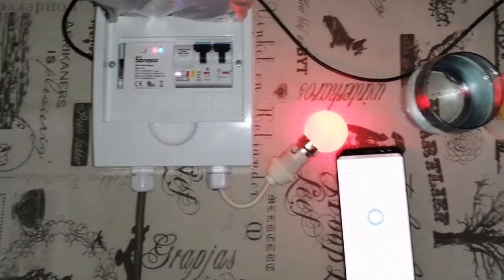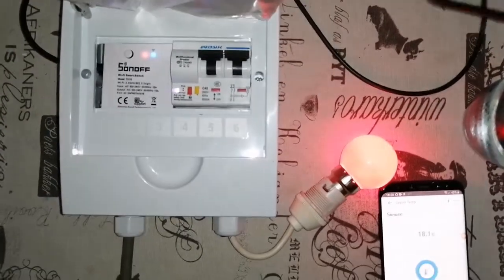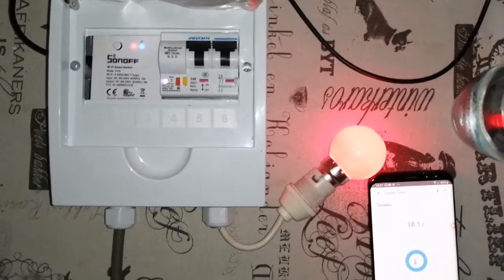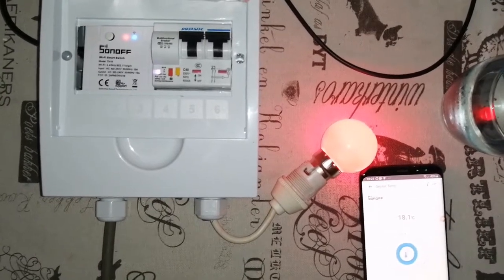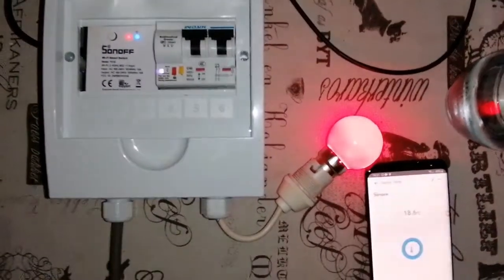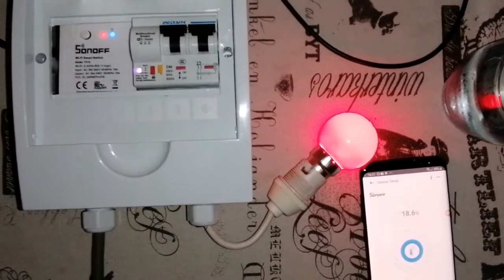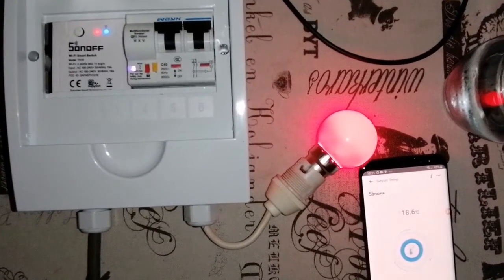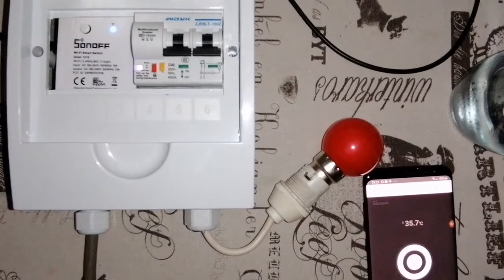Let's quickly just see what happens to the two switches. It is on — less than 25 degrees. I'm going to put it in the hot water. What will happen now is once the temperature reaches 30 degrees, the TH16 will switch off, and the eWeLink scene will then make sure that the circuit breaker switches off with it.